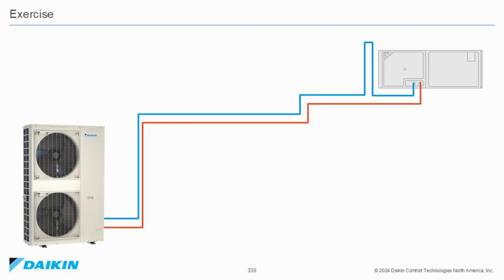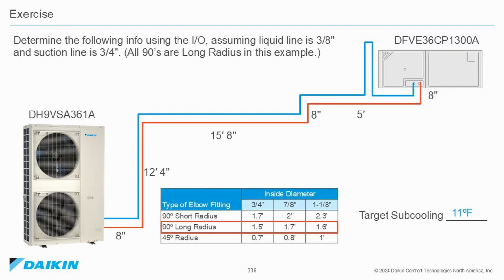Now let's do the exercise using a 2-fan 3-ton system. We will be using the DH9VSA361A outdoor unit and the DFVE36CP1300A indoor air handler. We will determine the following information using the I/O manual, assuming the liquid line is 3/8 and the suction line is 3/4, and all 90-degree elbows are long radius in this example. You'll see with the liquid line lengths shown here, our total line set length is 42 feet 5 inches. You'll also see the vertical line elevation using the 12-foot 4 rise, the 8-inch rise, and the 8-inch rise again at the indoor unit. We see that we have a total vertical elevation of 13 feet 8 inches.